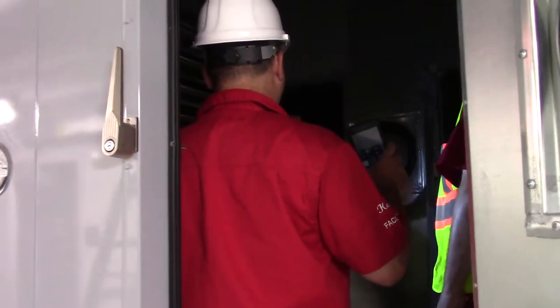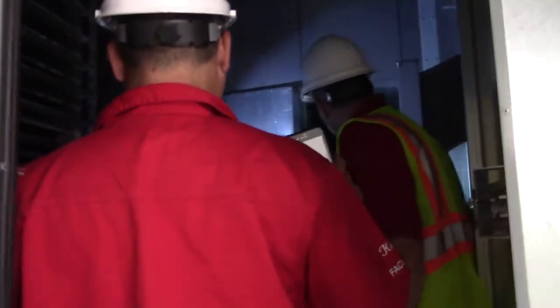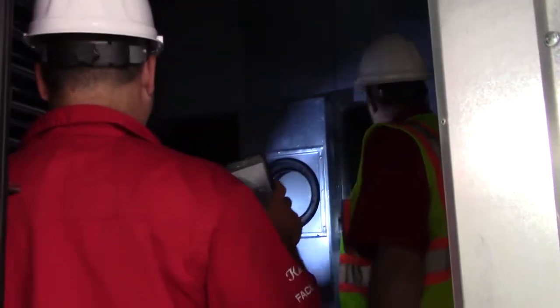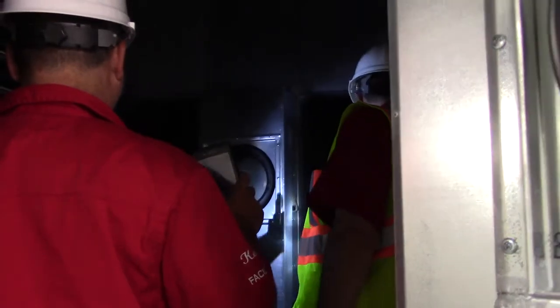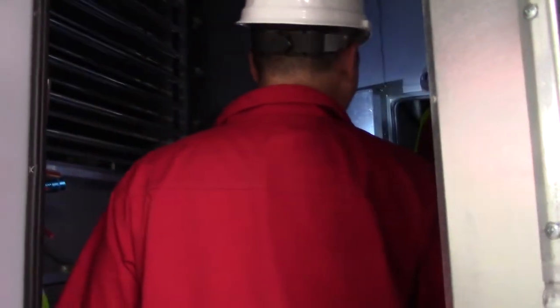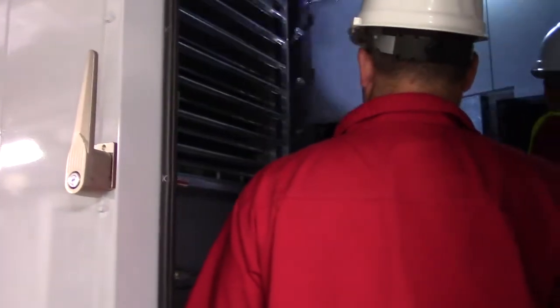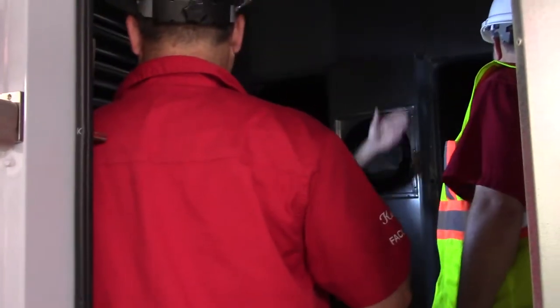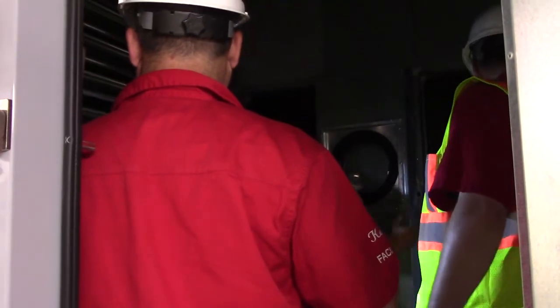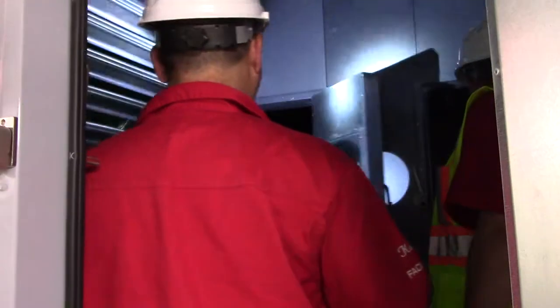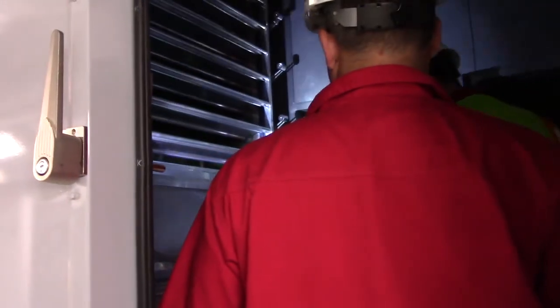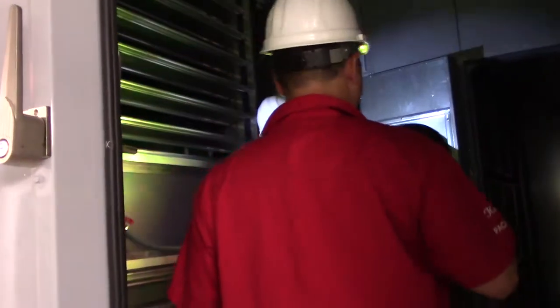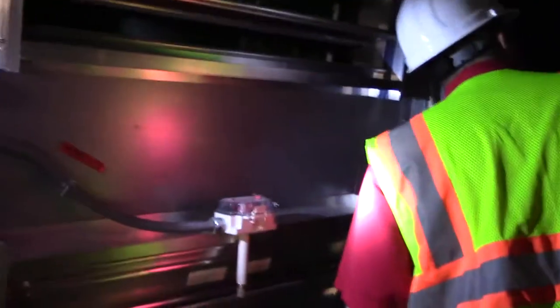This unit is basically split into 2 sections. One's a supply air section over here, and this would be the return air section. These doors are basically just to break off the sections. So you keep your supply air on one side, return air on the other side, and the only time they ever meet is coming through the heat wheel. And then to change the filters, they just have these little metal things that hold them in. You just bend those out of the way and you'll be good to go. I think that's it for this section.